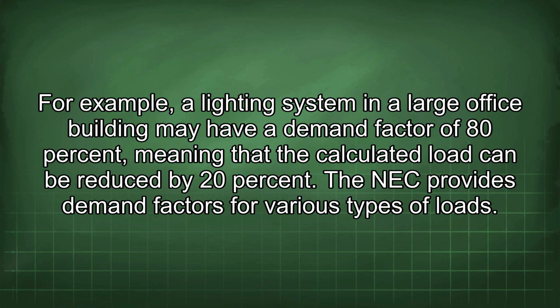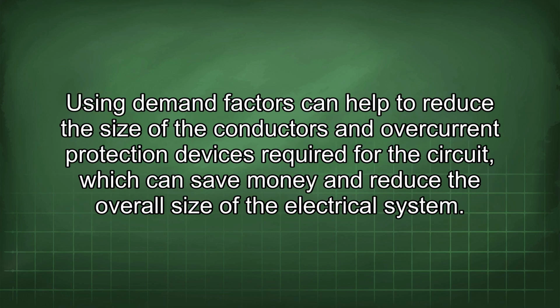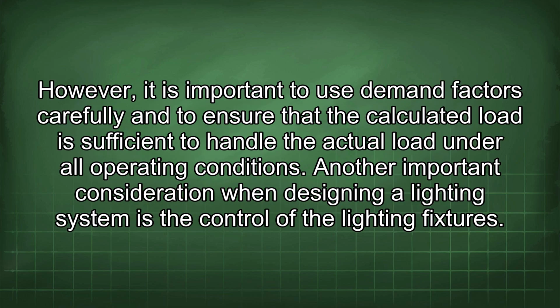The NEC provides demand factors for various types of loads. Using demand factors can help to reduce the size of the conductors and overcurrent protection devices required for the circuit, which can save money and reduce the overall size of the electrical system. However, it is important to use demand factors carefully and to ensure that the calculated load is sufficient to handle the actual load under all operating conditions.